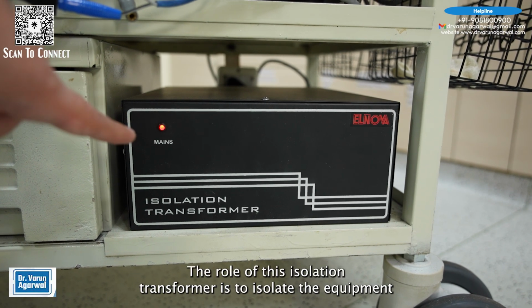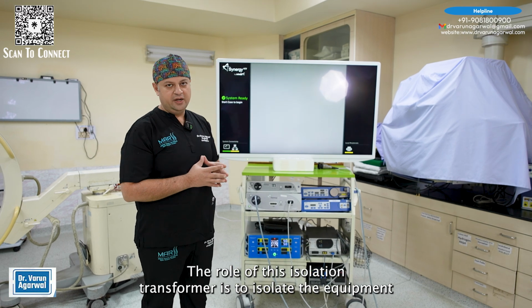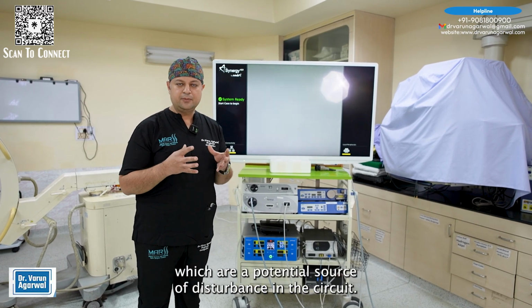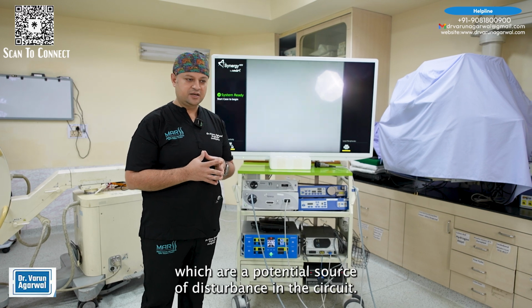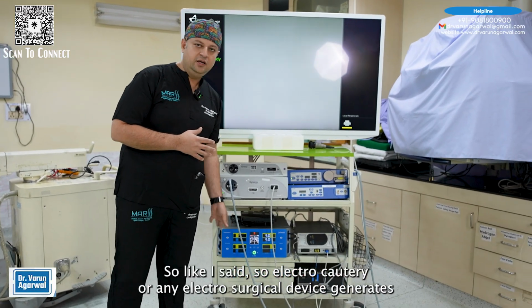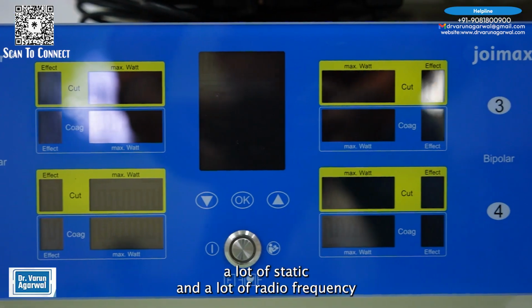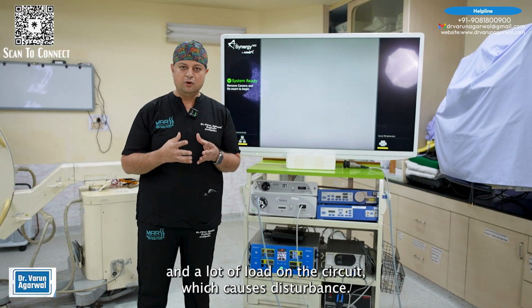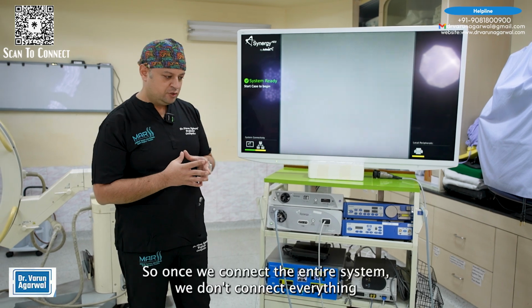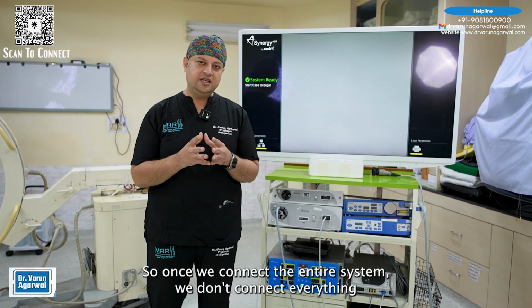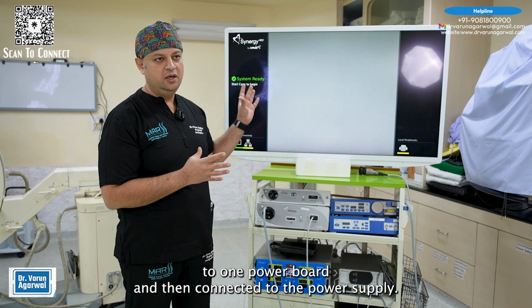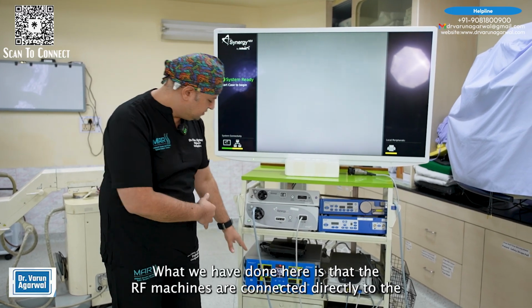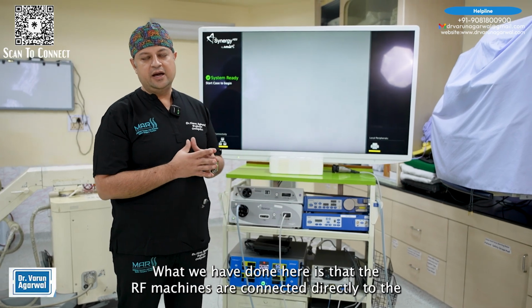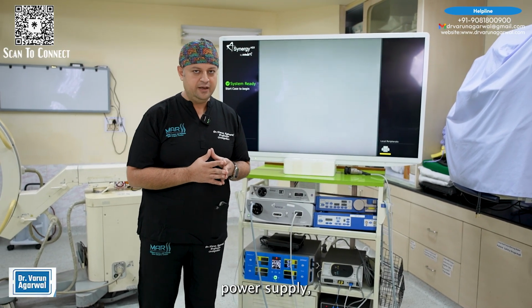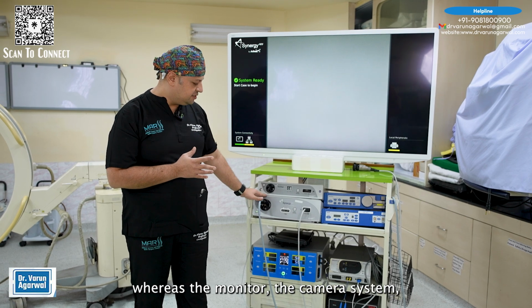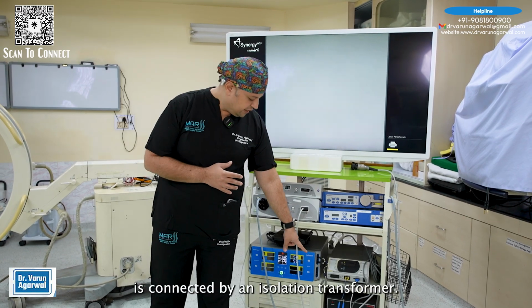The role of this isolation transformer is to isolate the equipment electrically from the other devices which are a potential source of disturbance in the circuit. Electrocautery or any electrosurgical device generates a lot of static and a lot of radio frequency and a lot of load on the circuit, which causes disturbance. So once we connect the entire system, we don't connect everything to one power board and then connect it to the power supply. What we have done here is that the RF machines are connected directly to the power supply, whereas the monitor and the camera system are connected via an isolation transformer.